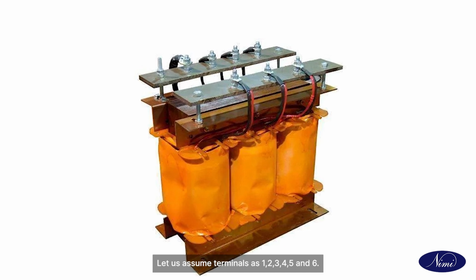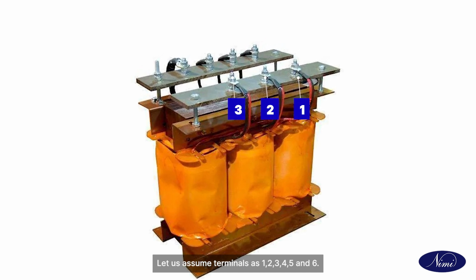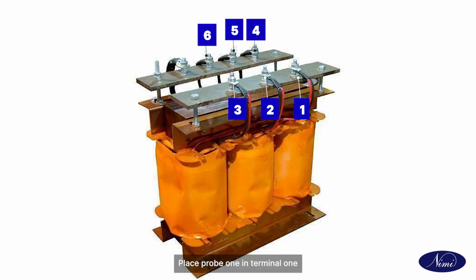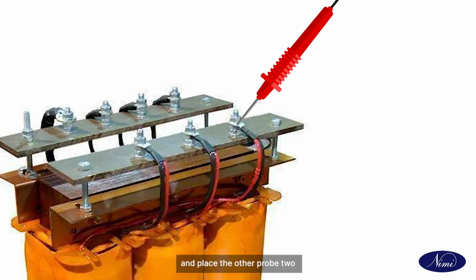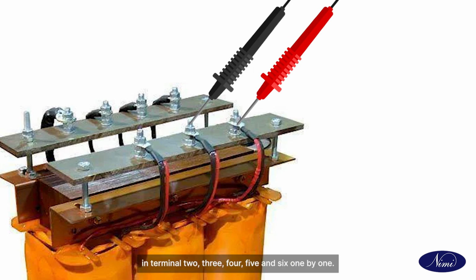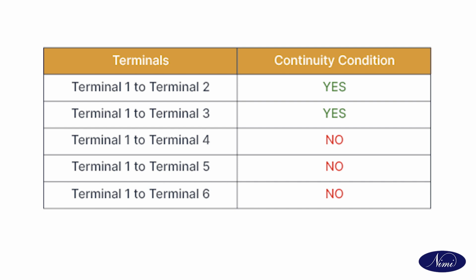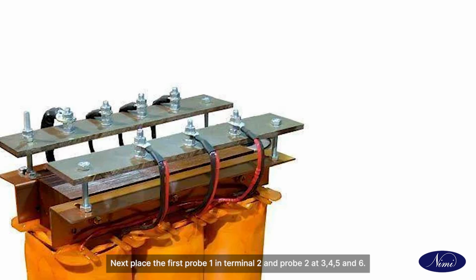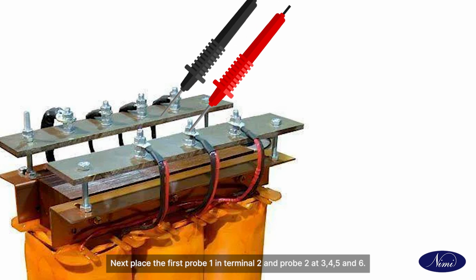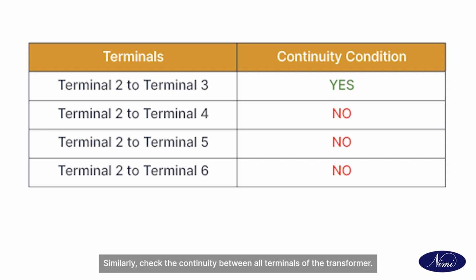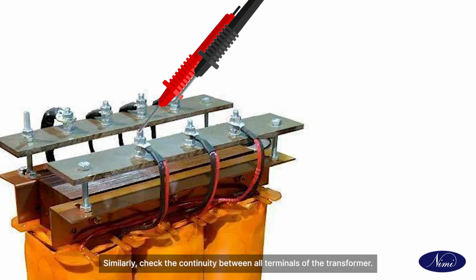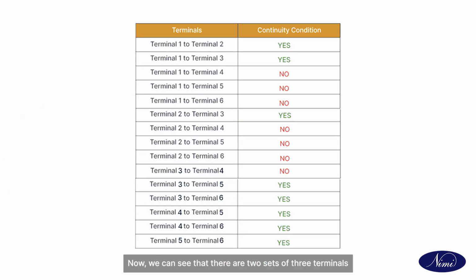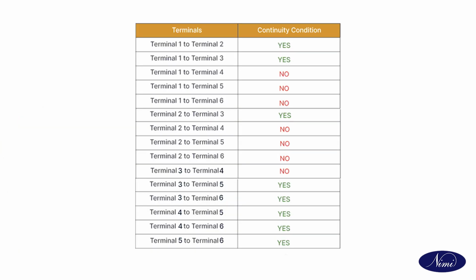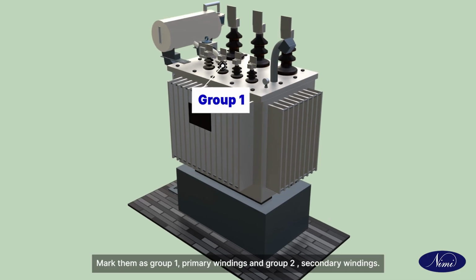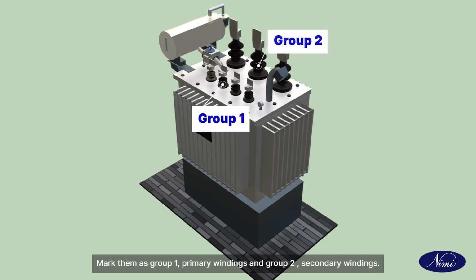Let us assume terminals as 1, 2, 3, 4, 5 and 6. Place probe 1 in terminal 1 and place the other probe 2 in terminal 2, 3, 4, 5 and 6 one by one. Record the condition in the table. Next, place the first probe 1 in terminal 2 and probe 2 at 3, 4, 5 and 6. Record the conditions. Similarly, check the continuity between all terminals of the transformer. Now, we can see that there are 2 sets of 3 terminals having continuity between them. Mark them as group 1 primary windings and group 2 secondary windings.